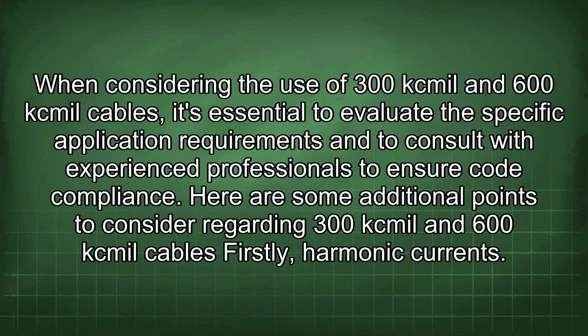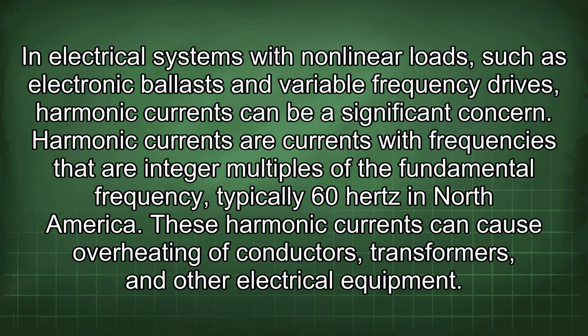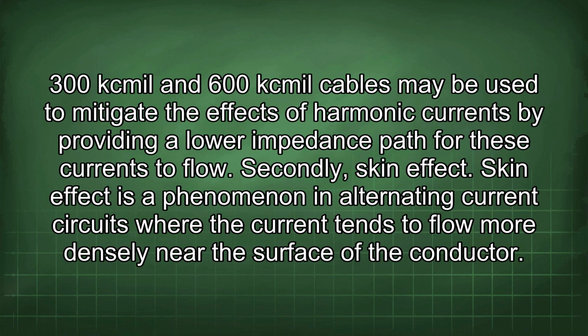Here are some additional points to consider regarding 300kcmil and 600kcmil cables. Firstly, harmonic currents. In electrical systems with nonlinear loads, such as electronic ballasts and variable frequency drives, harmonic currents can be a significant concern. Harmonic currents are currents with frequencies that are integer multiples of the fundamental frequency, typically 60 Hz in North America. These harmonic currents can cause overheating of conductors, transformers, and other electrical equipment. 300kcmil and 600kcmil cables may be used to mitigate the effects of harmonic currents by providing a lower impedance path for these currents to flow.